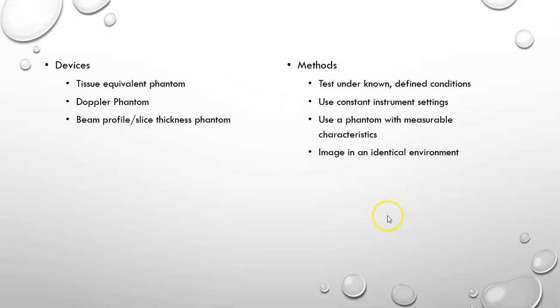The methods used are that you test under known defined conditions, you test regularly, you utilize the same equipment settings each time, you utilize a phantom with measurable characteristics, and you make an image in the identical environment. So you're going to have to set your lights at the same level every time you do quality testing. You're going to have to utilize a phantom that is certified. You're going to need to make sure that everything you're doing is set up the way you did it last time in order to see if there are any gradual changes. So that's all that means.